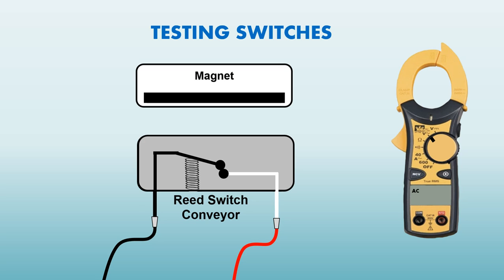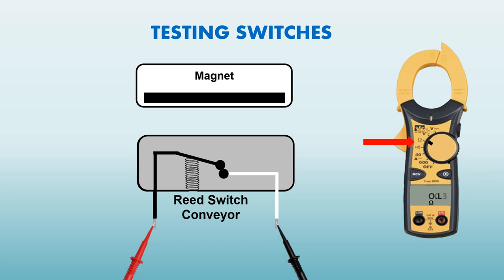Let's run one more example of testing continuity. Let's go back to the reed switch on a conveyor. As you notice, as the magnet is away, or if a rack is running through and the sequence bar removes the magnet, the switch is in the normally closed position.